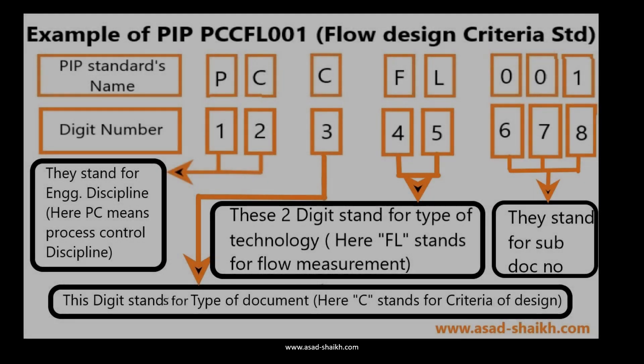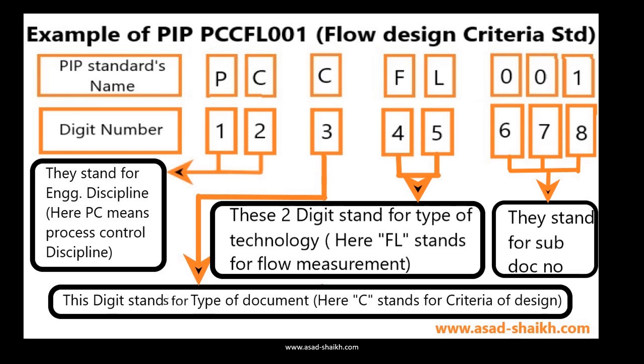To summarize: the first two digits stand for the type of engineering discipline; the third digit stands for the criteria of design or type of document; the fourth and fifth digits stand for the type of technology (flow meter, temperature, level, control valve, etc.); and the last three digits stand for the sub-document number.